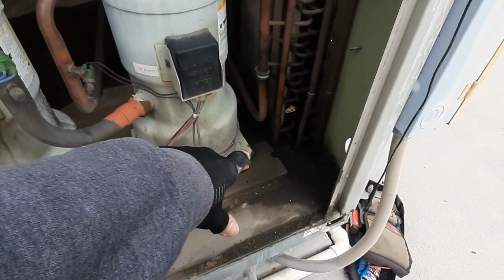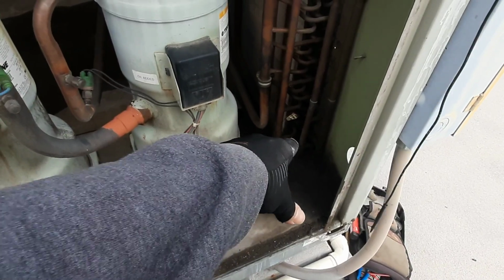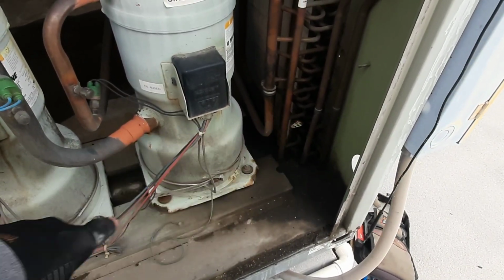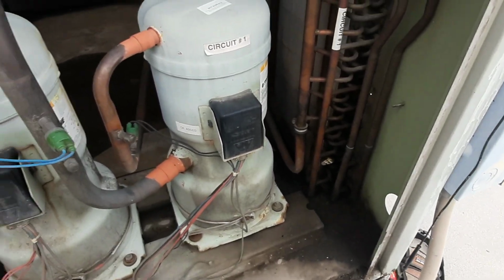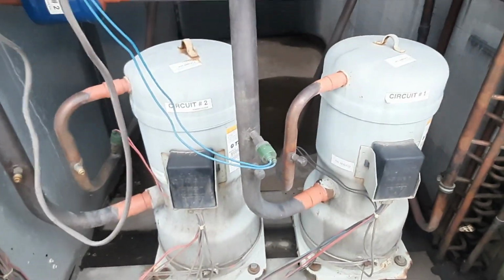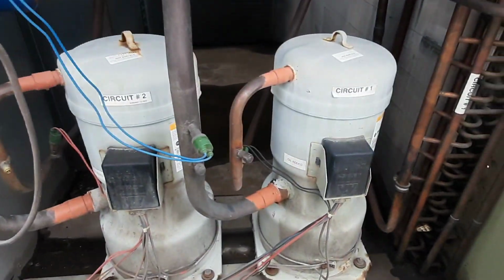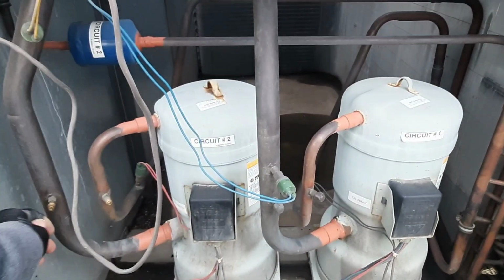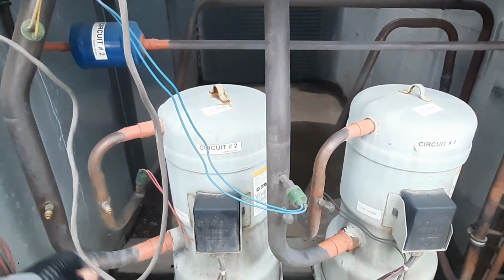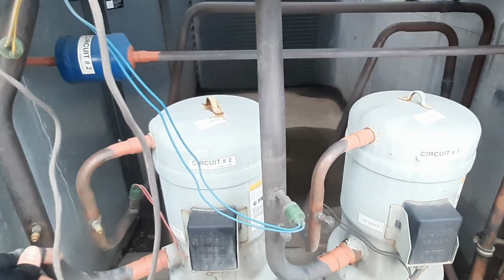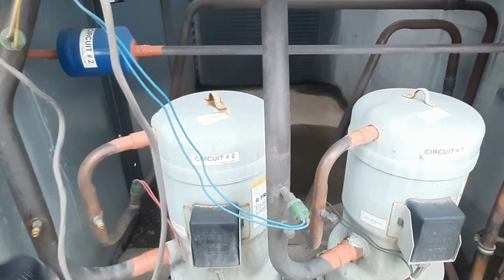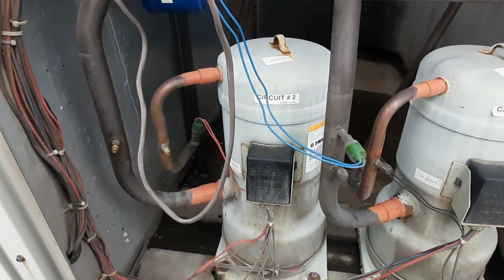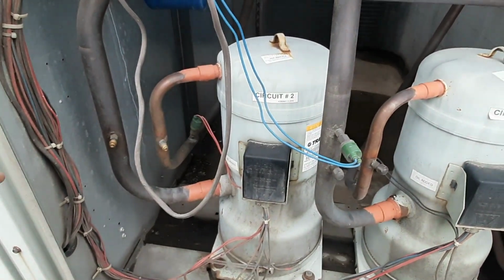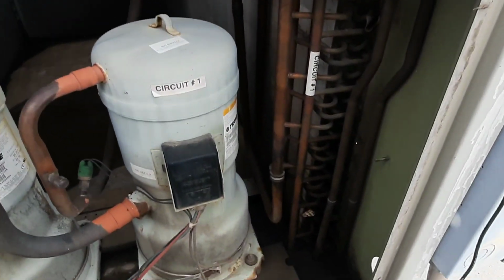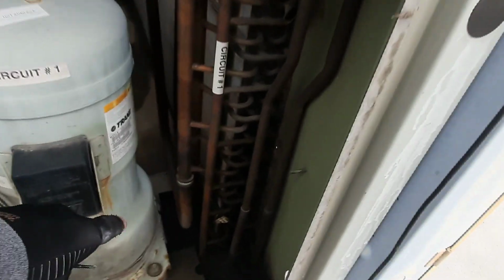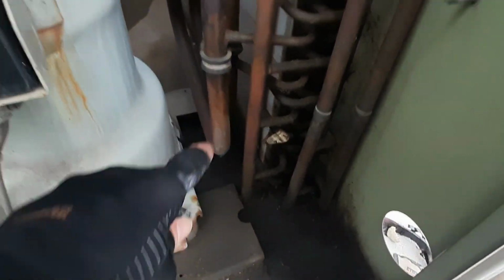You got your usual oil spots down here on the condenser. It's probably leaking. Somebody's had gauges on the thing, or at least on circuit 2. Oh, son of a bitch. I got pressure there. Could have had a leak repaired or something. These are typical leakers down here on the headers.